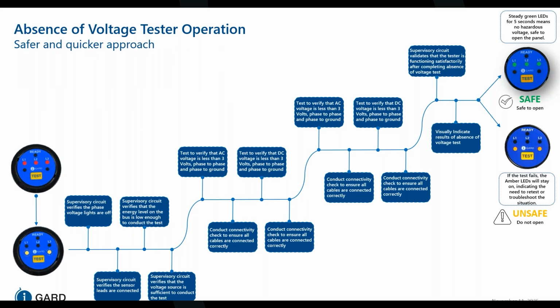The AVT performs multiple tests for AC and DC voltages across all phase-to-phase and phase-to-ground points, along with connectivity checks to confirm proper wiring. A built-in supervisory circuit validates the tester functionality before and after the test. When all checks pass, steady green LEDs indicate it is safe to open the panel, eliminating the guesswork and reducing the risk. If any of these steps fail, the AVT will show amber lights indicating a potentially unsafe situation.